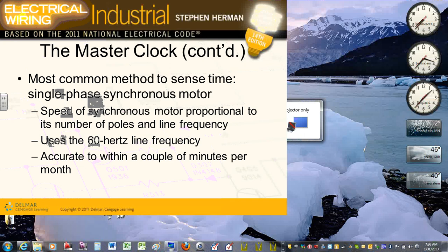And guess what was the issue with widening the gap? Motors, for the most part, don't care about adding one hertz or removing one hertz from 60 hertz. Guess what's going to be screwed up? Your synchronous motors, the time. You can screw up the time. So their argument is, with everybody going digital, why do we need these synchronous motors? Anyway, that was a big argument: adjusting the grid frequency will affect all these synchronous motors nationwide that are driven to get you the time. Everything else will be okay. And now with the digital world, people are saying they're becoming useless anyway. So just be aware of that one.